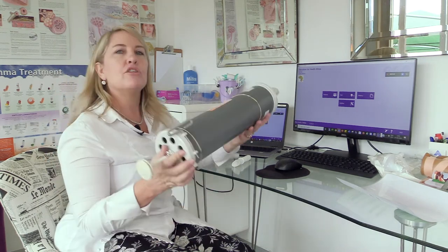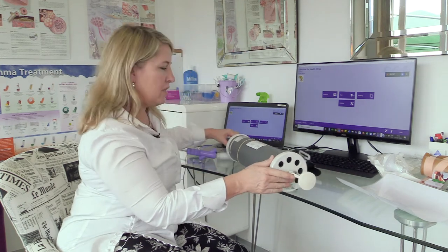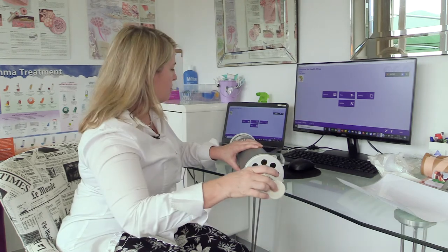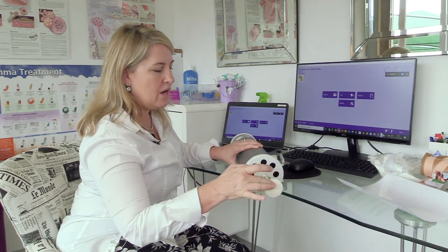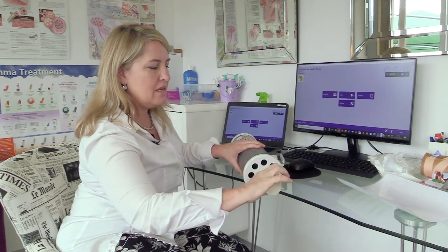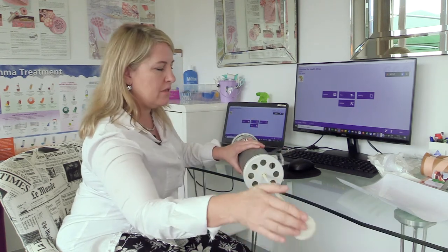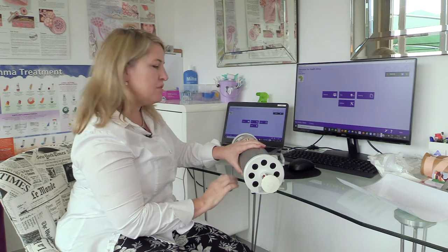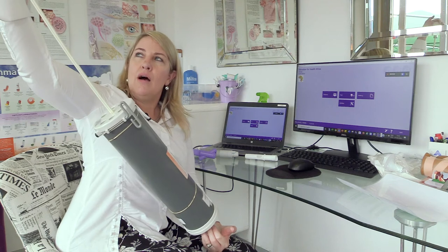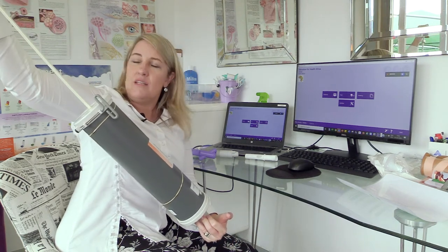The next thing is a smoothness check. I'm just checking that the plunger is moving nice and smooth. You can see I never press on the syringe handle with my full weight, because when you do that it often causes it to jiggle as it goes in. The syringe seems to be in very good working order. Now let me check for leaks — I occlude the outlet, push in the syringe handle, and there's no give.